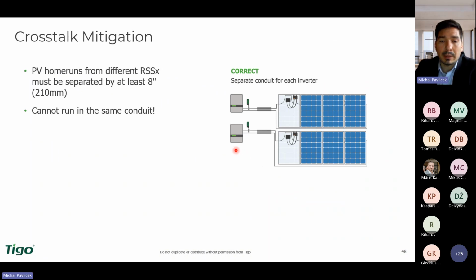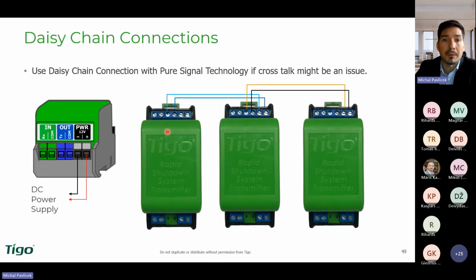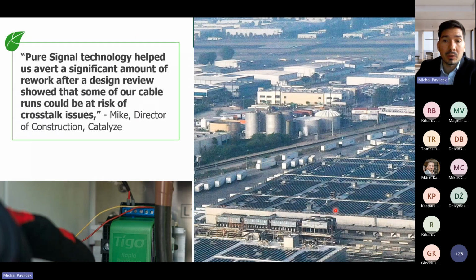What is also very great is that when you have a big project with more inverters, there are more RSS transmitters, each sending the signal. To avoid the signal being lost due to crosstalk in the channels where we have the cables, we have patented a solution of synchronizing the transmitters. You can connect up to 10 transmitters together to synchronize them. The first one, on the first line, works as the master, the rest are the followers, and it sends the signal in one moment, which is able to operate even very large projects like you see this one in the US. So even the very large projects can be operated with this very simple and robust solution.